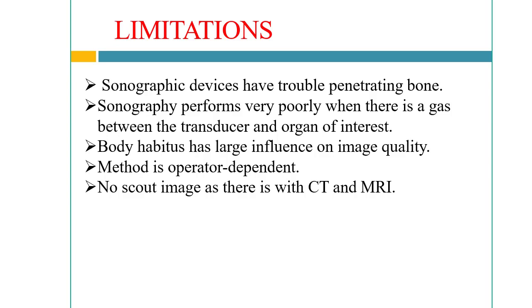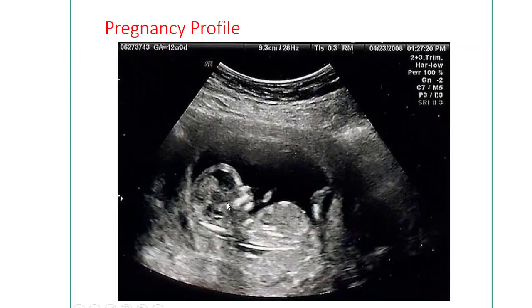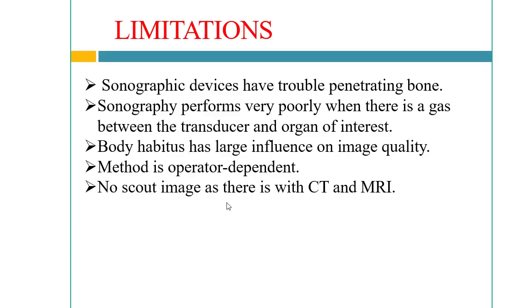There are also some limitations of ultrasonography. Sonographic devices have trouble penetrating bone. Sonography performs very poorly when gas is present between the transducer and the organ of interest. Body habitus has a large influence on image quality. The method is operator-dependent. Unlike CT scanners or MRI, no scout or pilot film is available in ultrasonography.